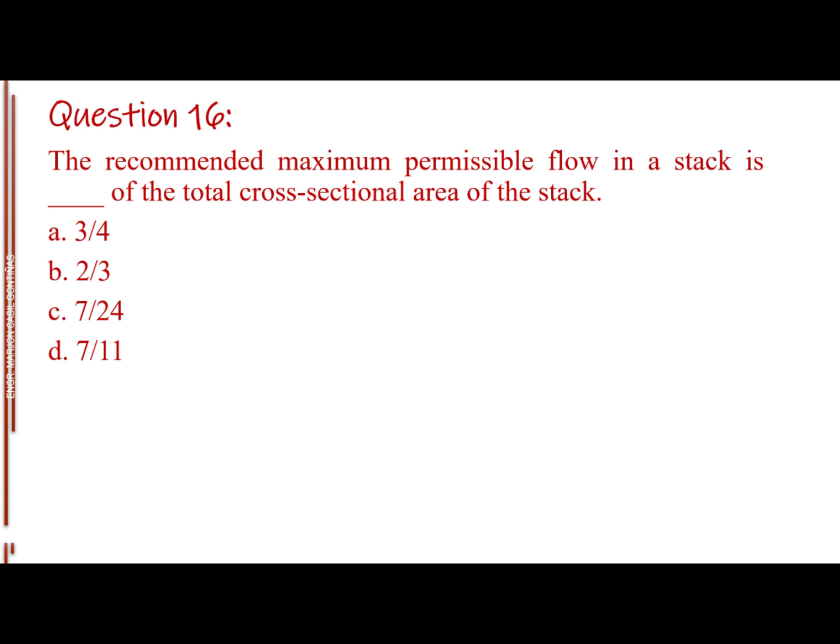Question number 16. The recommended maximum permissible flow in a stack is blank of the total cross-sectional area of the stack. Letter A, Three-Fourths. Letter B, Two-Thirds. Letter C, Seven Over Twenty-Four. Letter D, Seven Over Eleven. The answer is Letter C, Seven Over Twenty-Four.